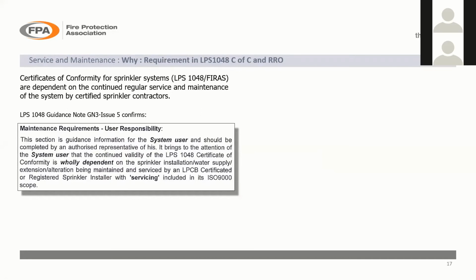So first of all, we're going to talk about why they're required. Obviously, Dale talked about certification and certificates of conformity, and in particular LPS 1048 certificates, which are issued as part of the 1048 scheme. It is a requirement that for maintenance of that certificate, your system is maintained by a sprinkler maintenance contractor for the continued validity of the certificate itself. So if you don't maintain it, you compromise the validity of the certificate. Just bear in mind that not all systems have a 1048 certificate, but where they do, it is a requirement that the system is maintained in accordance with the standard.